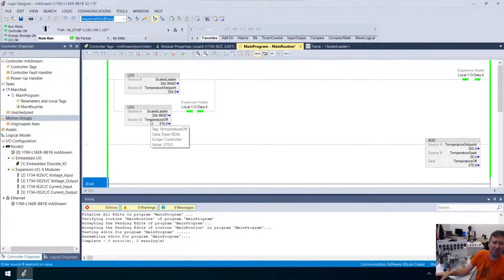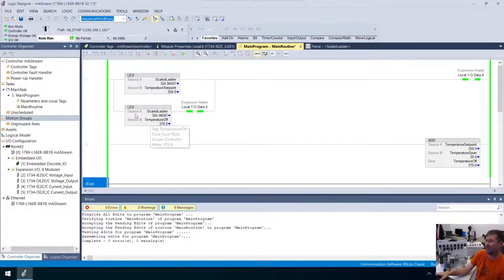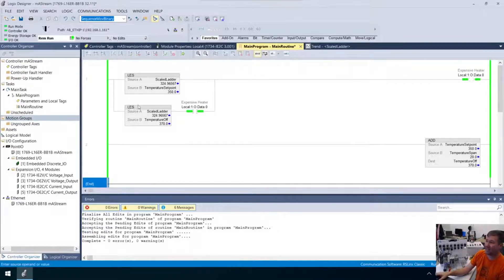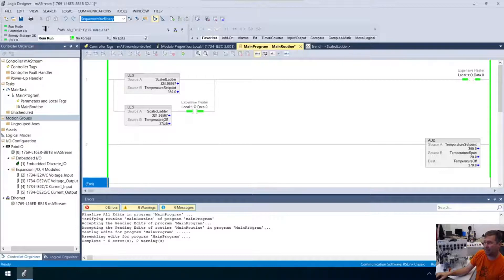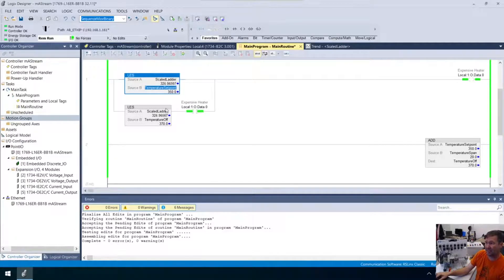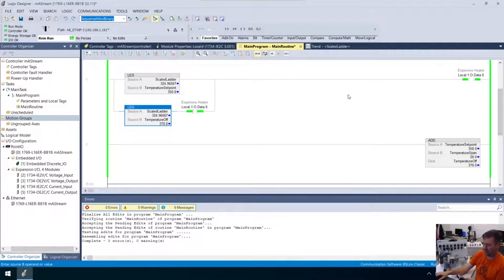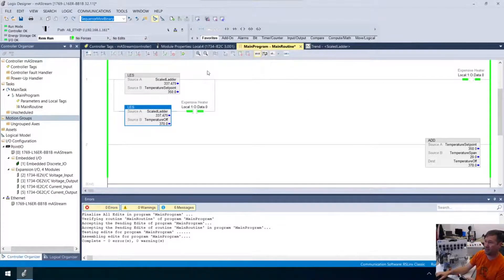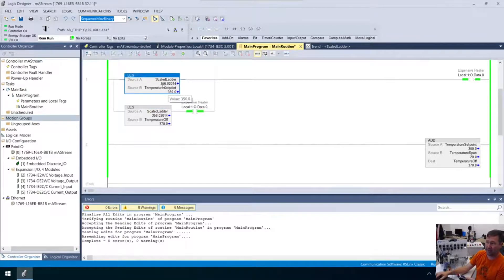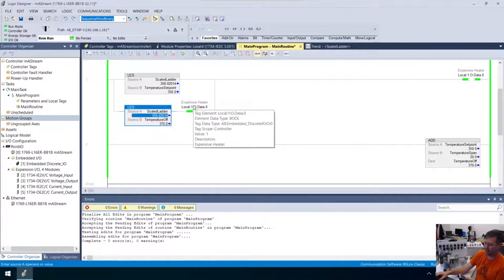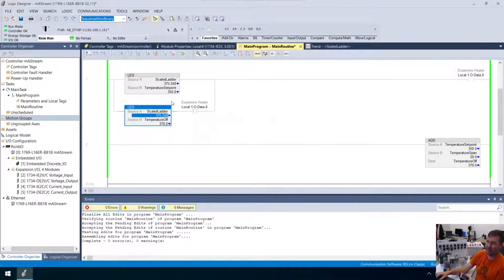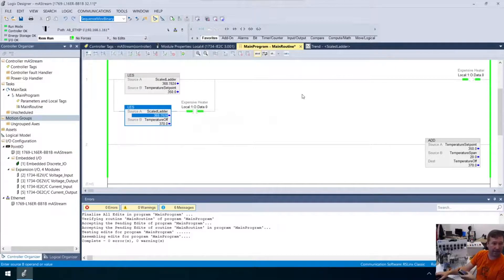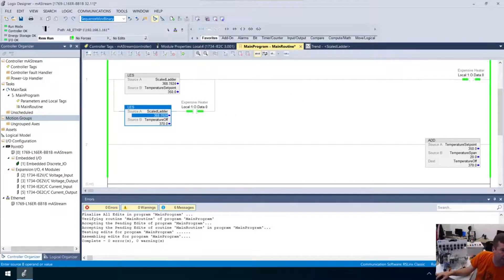Now the one thing you have to pay attention to is now the span in the next rung, is typically you want, now this would actually work. This will work just fine. But what you want to do is you want the set point that the operator enters to be when he sees that on action. It's going to keep him from asking questions. So in this case, I want to add now. So what we're going to do is we're going to heat, we're going to kick the heater on when we're below a temperature. And now we're going to keep heating until we get above a certain temperature. Let's throw that in so you can see the values change on this. All right, now our high is 370. Now again, this may be way too much range. Y'all may be like, well, who wants an oven that's between 350 and 370. I'm just making these values wide so you can see exactly what's going on. But all right, now our span is going to be, we're going to start if it's less than 350. And they're going to keep running until it's at 370. So we're at 324 right now. Our heater is running.